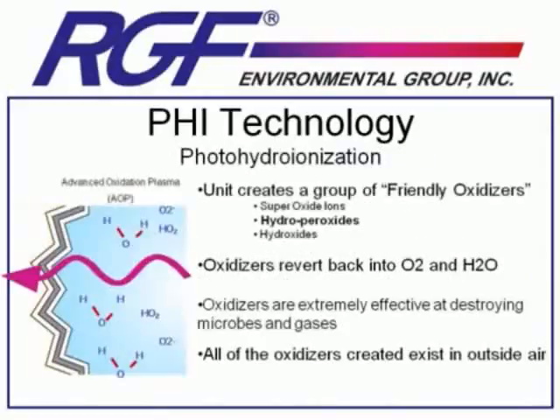When the UV bulb in a PHI system is energized, it shines light onto this quad metallic catalyst. Much like the photoelectric effect shown earlier, it creates electron holes, which start a chain reaction with molecules in the air. Because we're using a quad metallic catalyst, we're able to generate different oxidizers than just hydroxyl radicals, one oxygen and one hydrogen. The strongest of these are hydroperoxides, or H2O2.